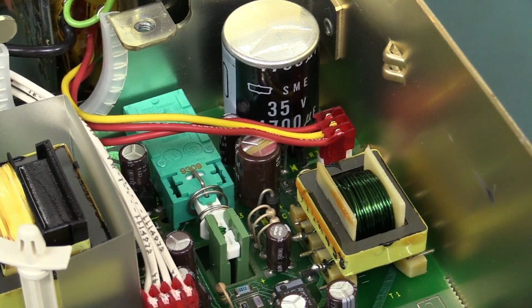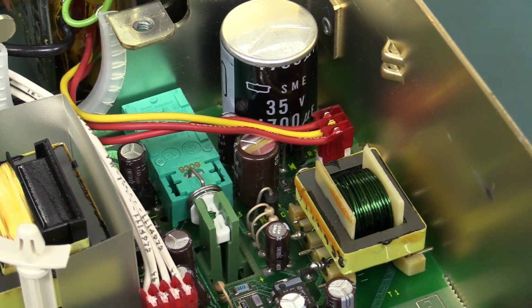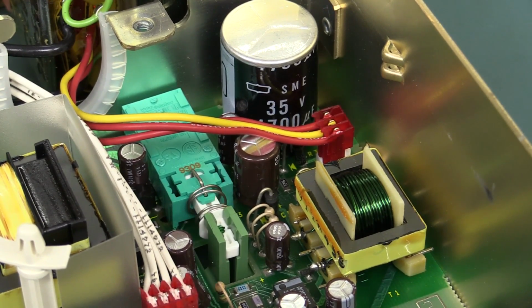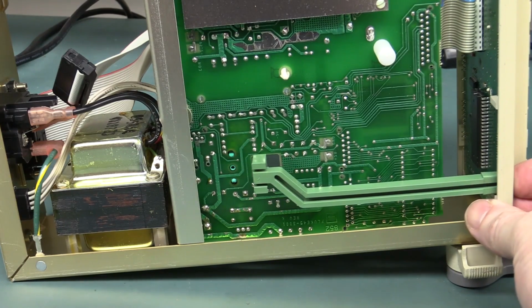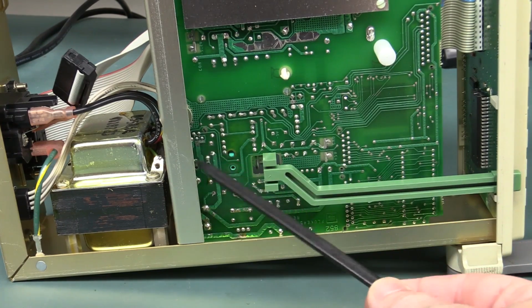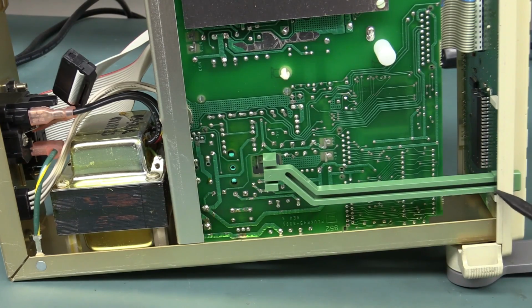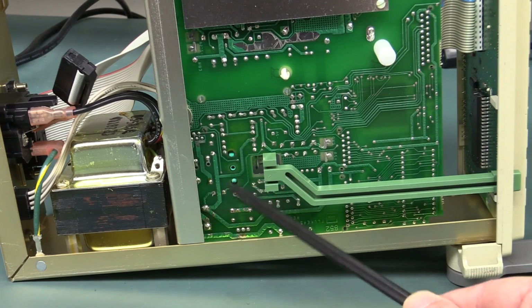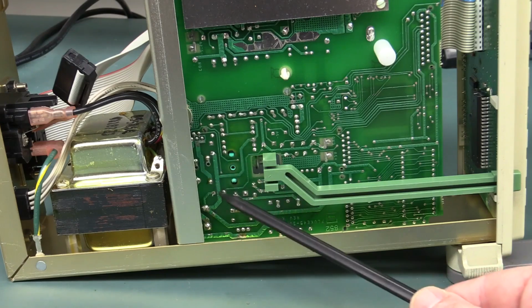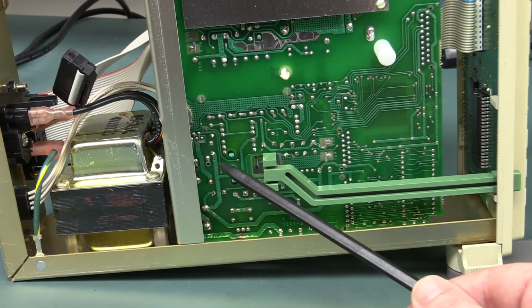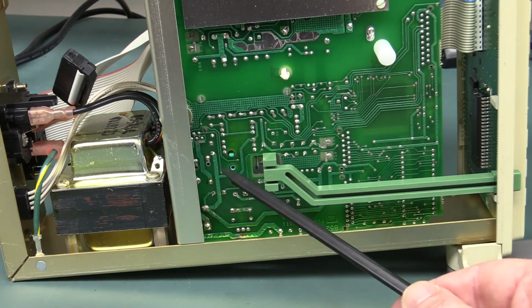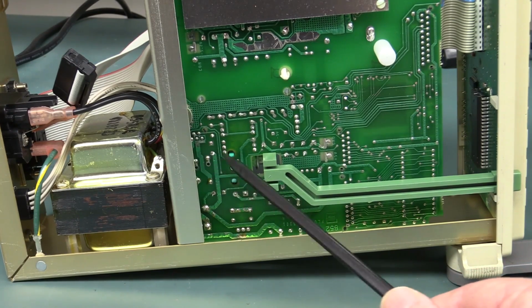You'll notice that the switch is right back here on the PCB. Why is it so? You should know that I'm a big fan of those push rods and having the switches all the way back rather than run cables right to the front. That's really messy. They've put the switch right where it needs to be on these high current traces for switching, well, they've got to switch in between the battery and the mains transformer. So that's not a mains switch.